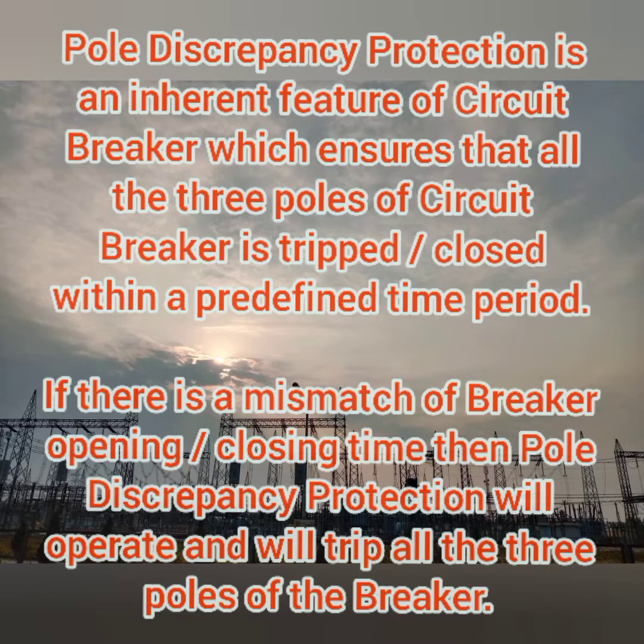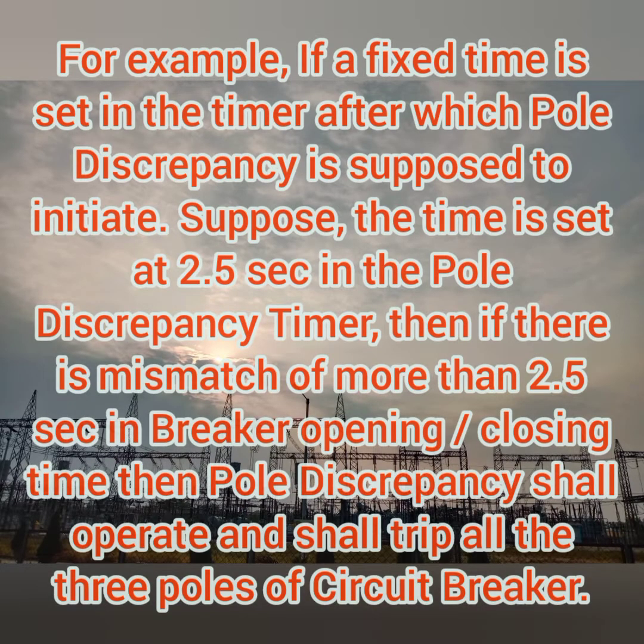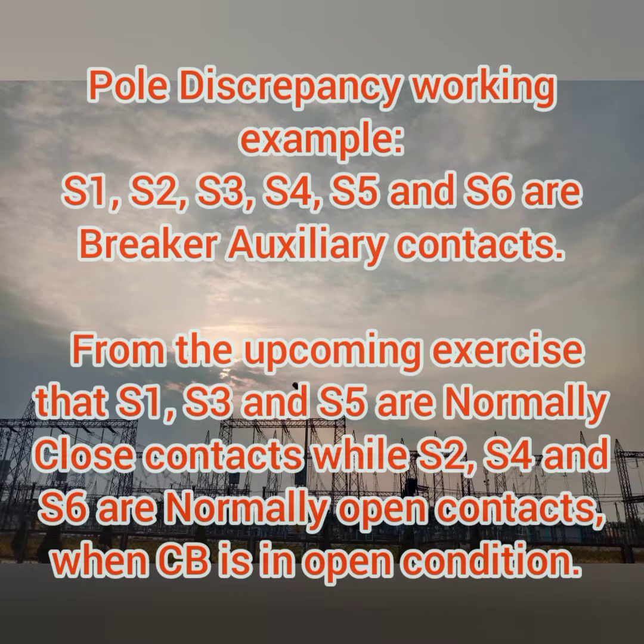Pole discrepancy is used to check the opening and closing of your circuit breaker. It is assisted by a timer and checked by its breaker auxiliary contacts. For example, if a fixed time is set in your timer — suppose the time is set at 2.5 seconds — then if there is any mismatch, meaning the opening and closing is taking place after 2.5 seconds, the pole discrepancy shall initiate and give the trip command for all three poles of your breaker.